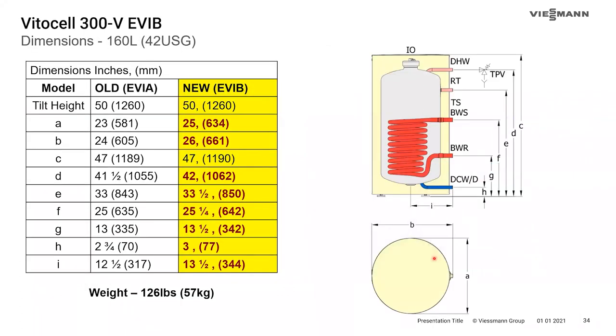Looking at the dimensions table — this is in the TDM and the flyer so it doesn't need to be memorized — but if you're replacing an older EVIA tank with an EVIB, be aware there are slight dimensional changes in some sizes regarding where the pipe connections are made. Don't assume it will be a direct match; you will need to make some slight piping changes if you've rigid-piped it.